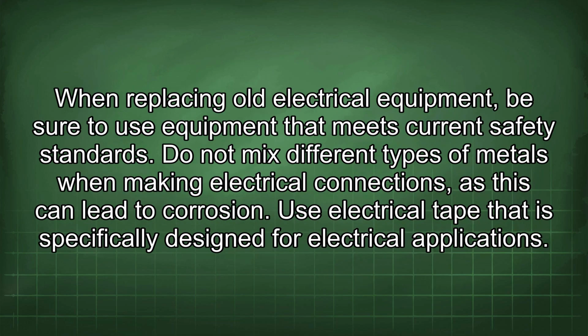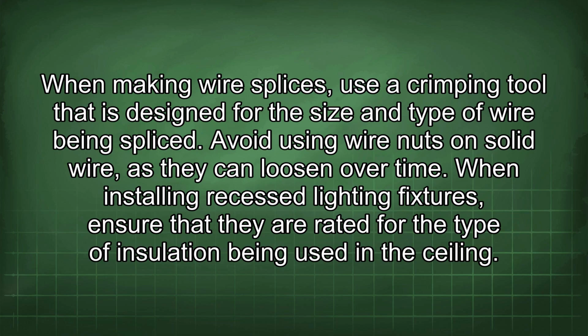When replacing old electrical equipment, be sure to use equipment that meets current safety standards. Do not mix different types of metals when making electrical connections, as this can lead to corrosion. Use electrical tape that is specifically designed for electrical applications. When making wire splices, use a crimping tool that is designed for the size and type of wire being spliced. Avoid using wire nuts on solid wire, as they can loosen over time.